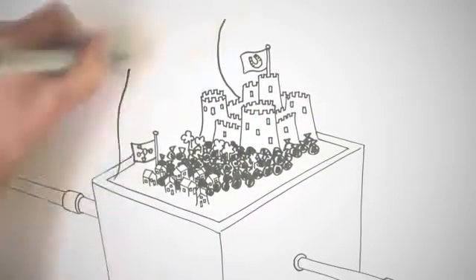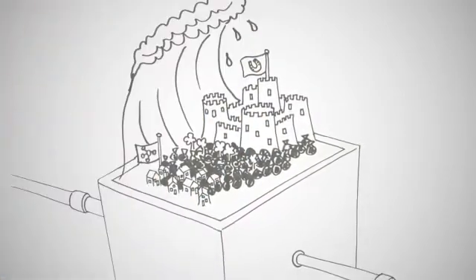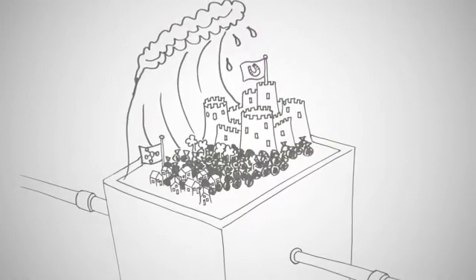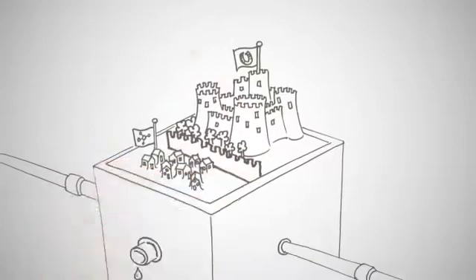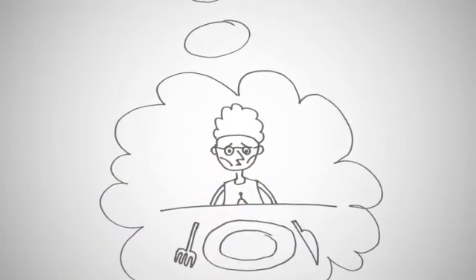The iron-eating bacteria left a lot of rubbish in the sand filter, which we soon had to clean up. This was a problem as the ammonium removers were just starting to adjust to their new home. Additionally, the iron-eating bacteria claimed all the food, namely the phosphate. This led to starvation of the more modest ammonium removers.